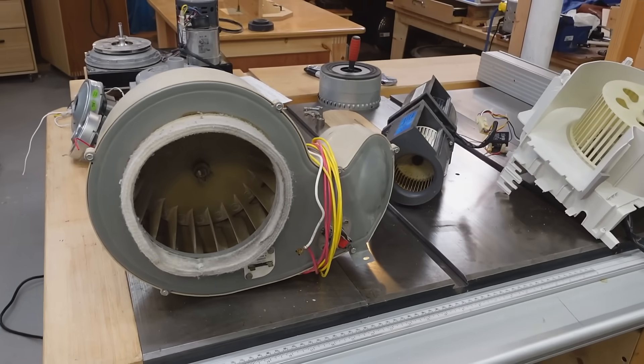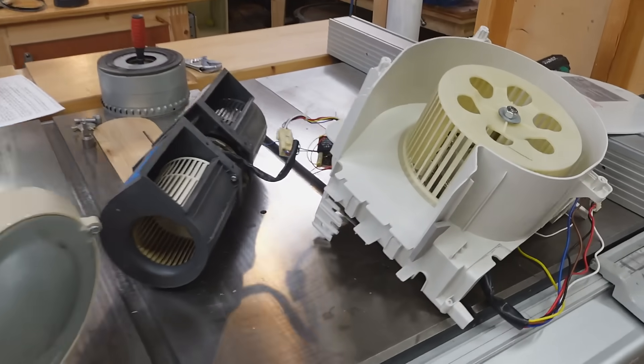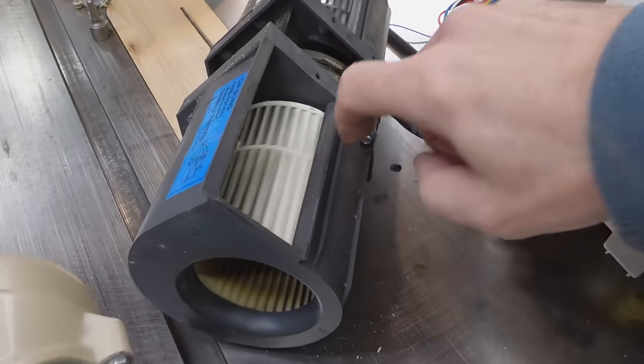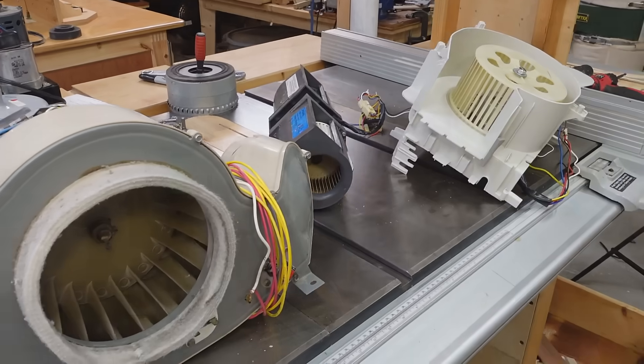Looking at blowers with forward facing fins: this one's from a dehumidifier, this one's a range hood, this one's from a clothes dryer, this one's for a furnace. They all have scroll cage with forward facing fins, and these all run at fairly low RPM, and therefore moving lots of air at very low pressure.